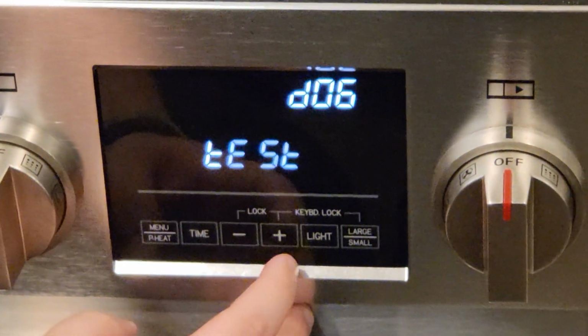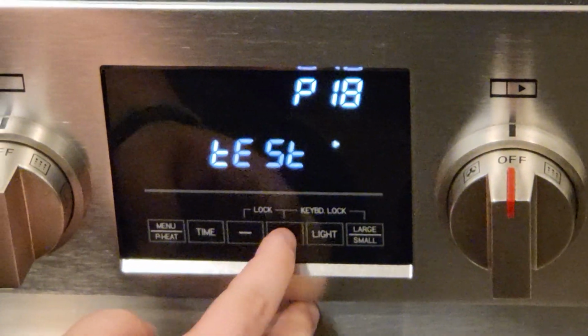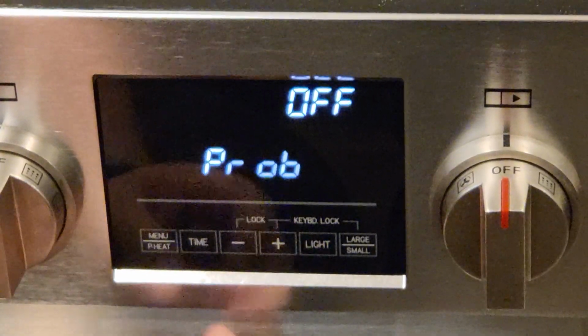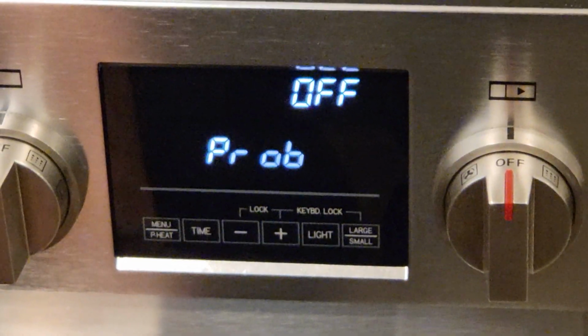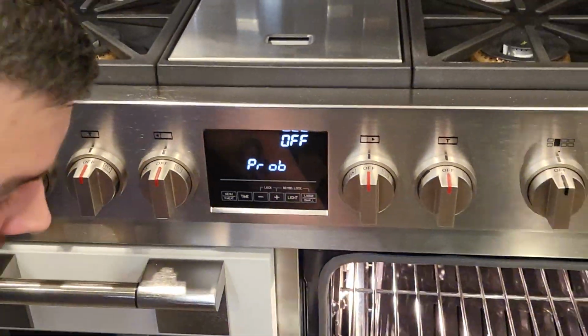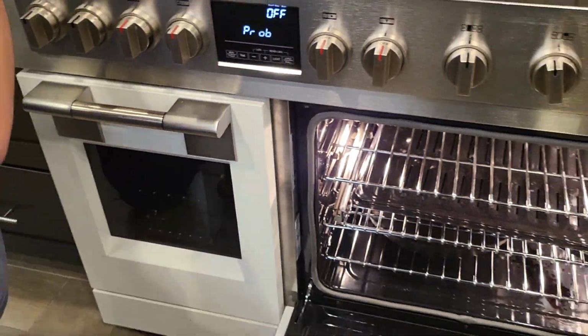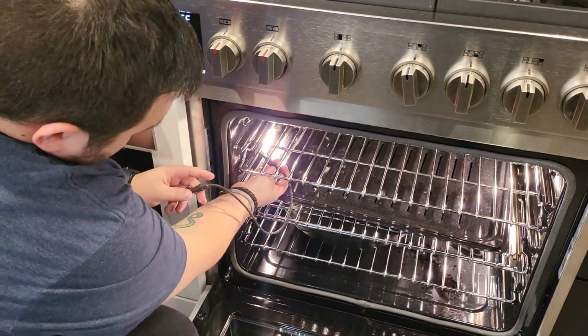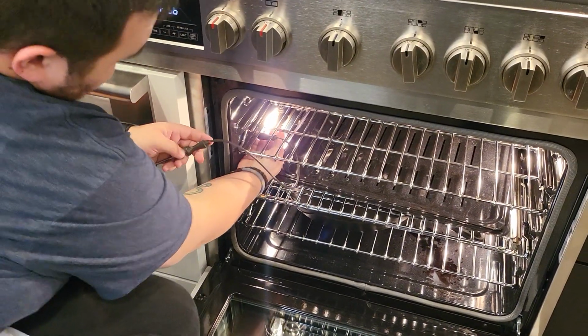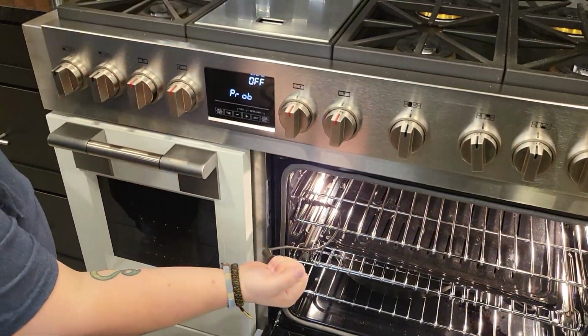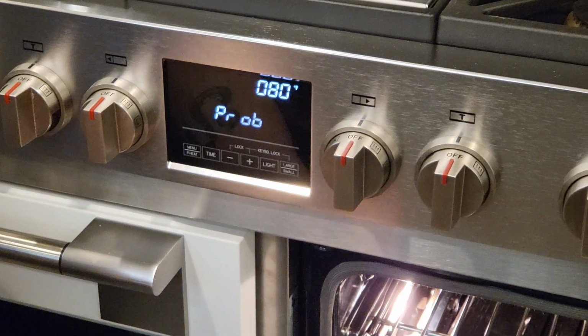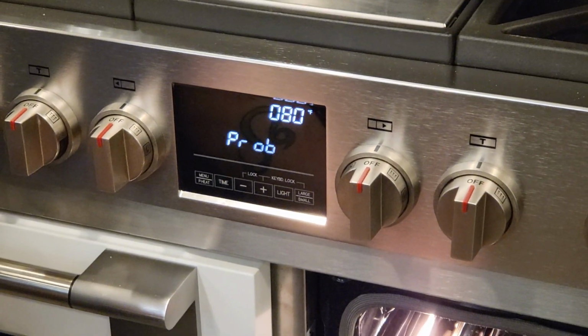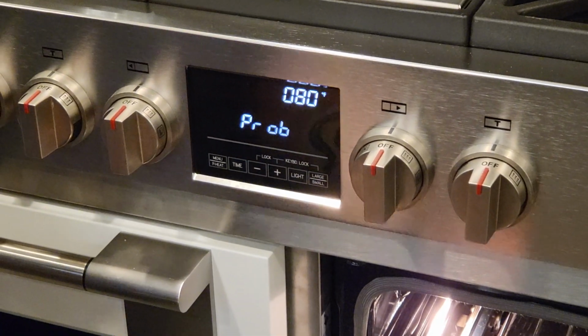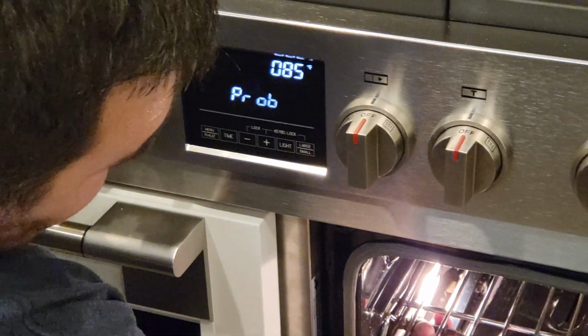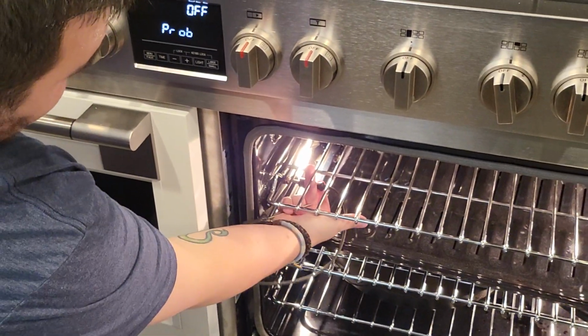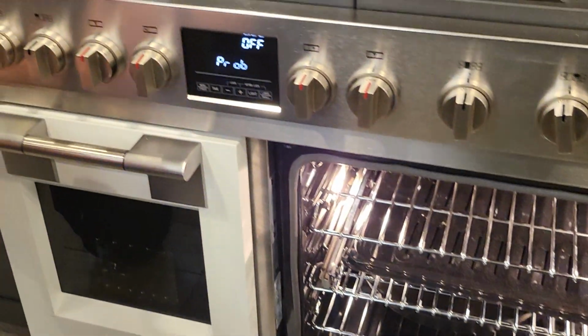We're going to continue forward until we get to probe. So we have probe off. We're going to calibrate the probe by plugging it in. Once it's plugged in, wrap your hand around the end of the probe and you should start to detect the body temperature of your arm or hand. So we've confirmed this is working. We're going to go ahead and unplug it. It should go back to off on the display and we can continue forward.